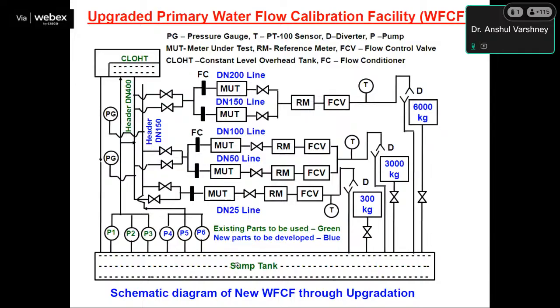The capacity of this underground water tank is 2,25,000 liters, and its dimensions are 30 meters in length, 3 meters in depth and 3 meters in width. There is an overhead tank of 21,000 liters at a height of 25 meters, and we have 5 dedicated lines: 25 mm, 50 mm, 100 mm, 150 mm and 200 mm. We provide calibration in this facility from 10 liters per hour to 6,50,000 liters per hour, and as I told earlier, we have 3 scales.